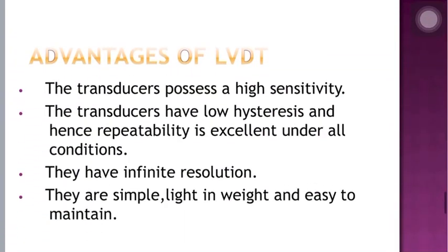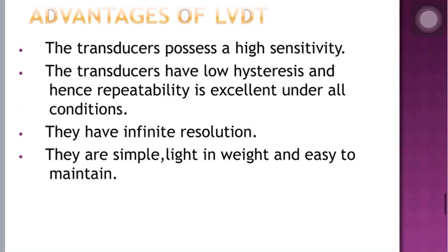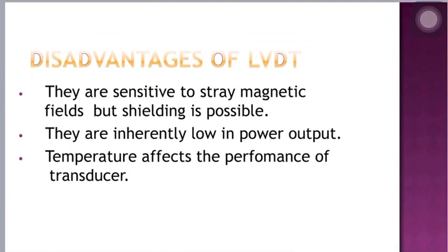And coming to the advantages of LVDT, the transducer possesses high sensitivity and low hysteresis, and hence repeatability is excellent under all conditions. They have infinite resolution, they are simple, light in weight and easy to maintain. Coming to disadvantages, they are sensitive to stray magnetic fields, but shielding is possible. They are inherently low in power output. Temperature affects the performance of the transducer.